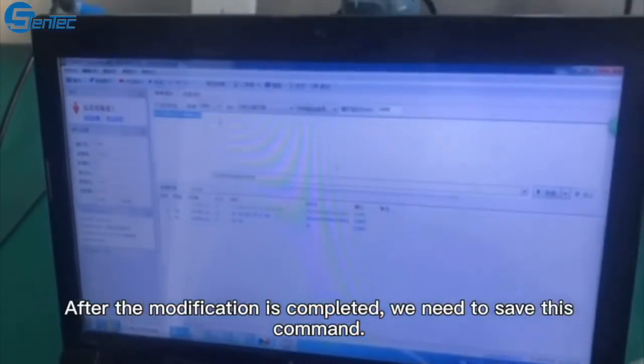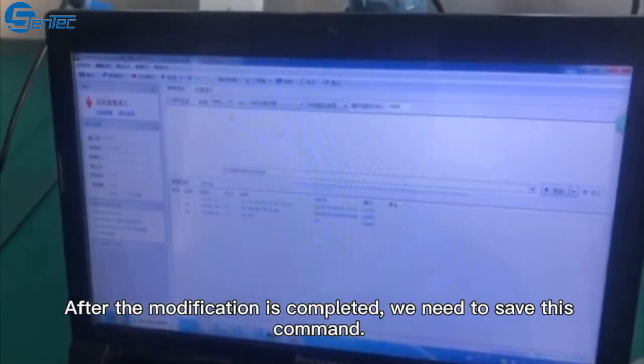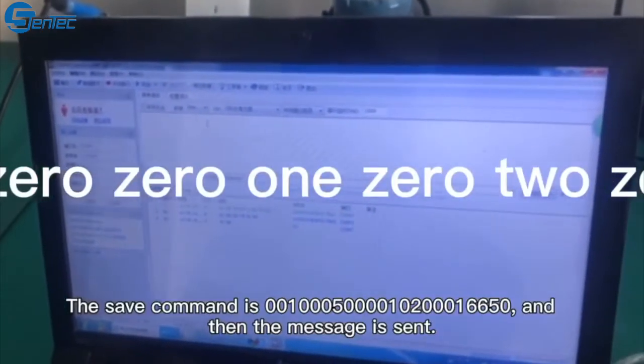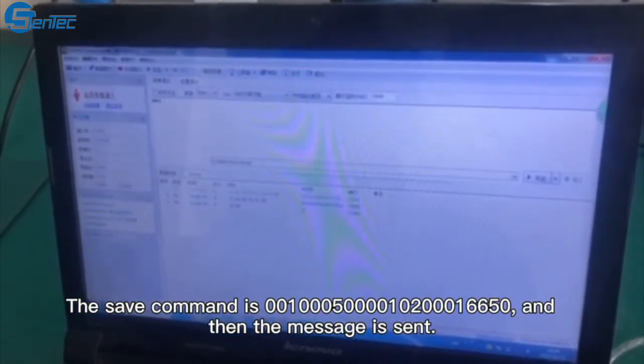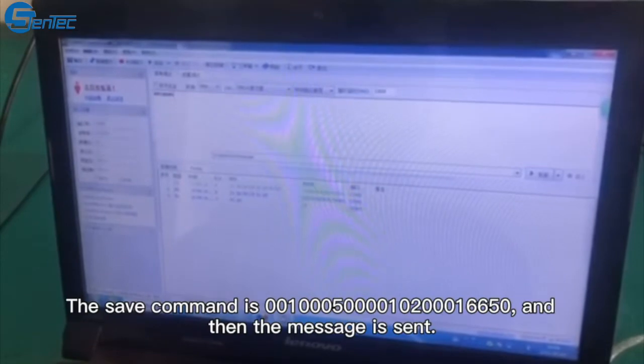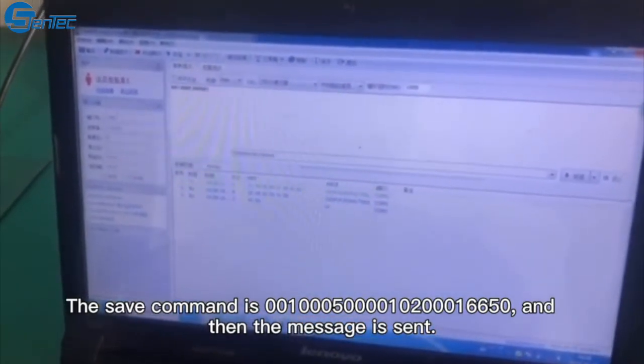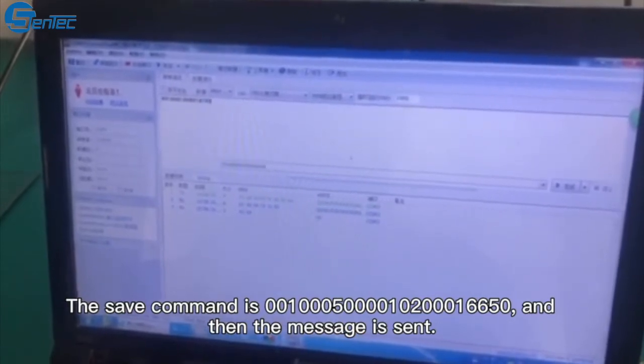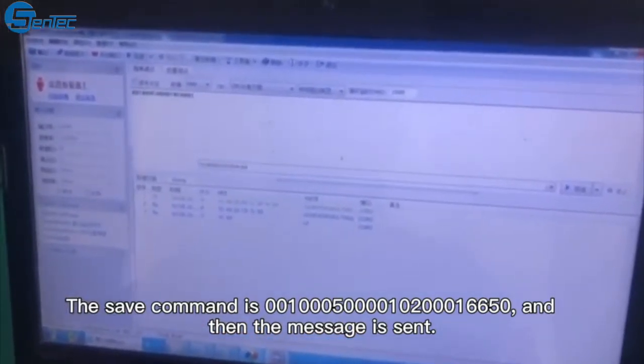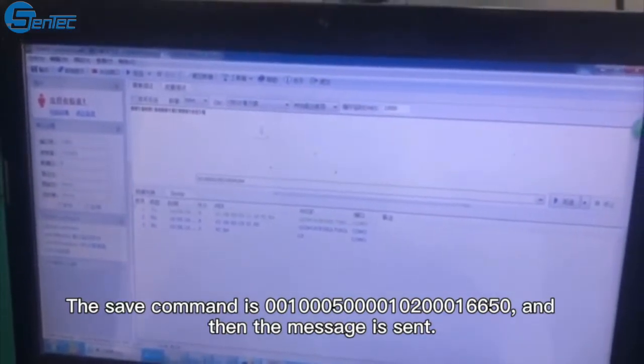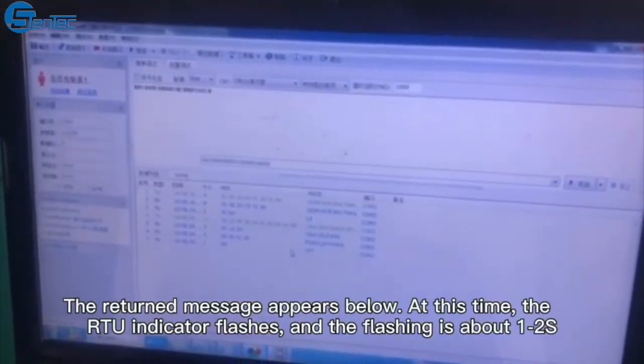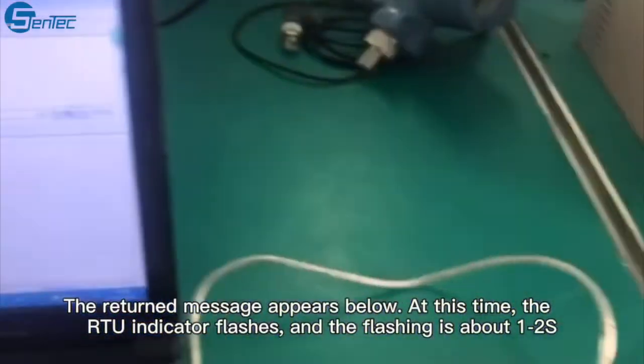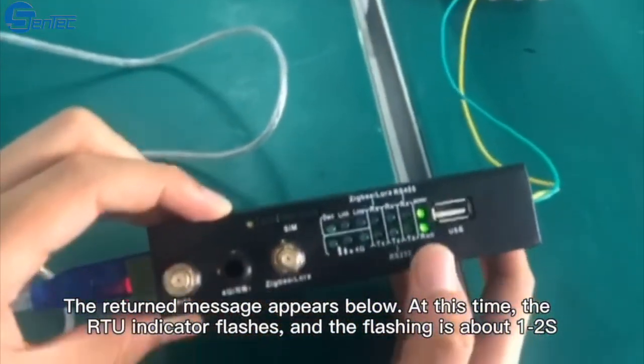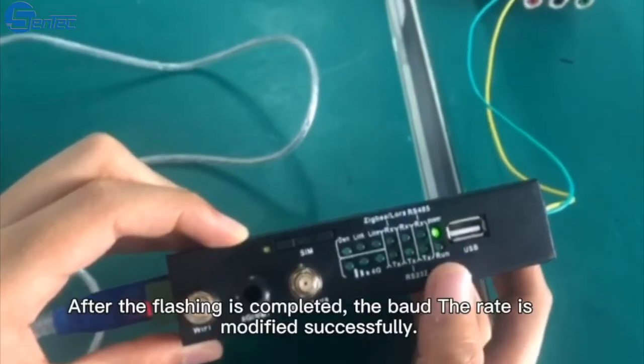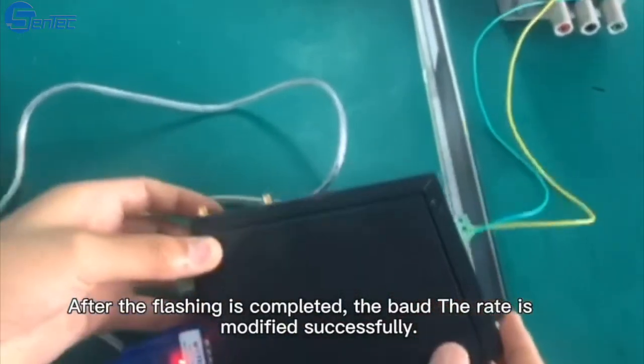After the modification is completed, we need to save this command. The save command is 0010005000010200016650. The return message appears below. At this time, the RTU indicator flashes, and the flashing lasts about 1 or 2 seconds. After the flashing is completed, the baud rate is modified successfully.